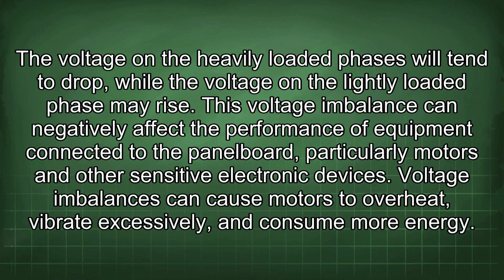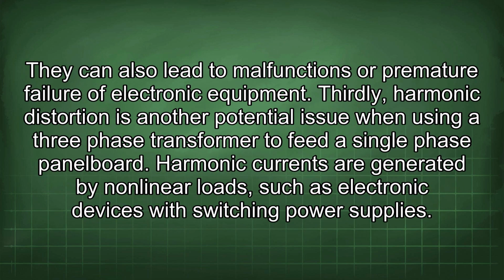Secondly, voltage imbalances can occur when a 3-phase transformer is subjected to an unbalanced load. The voltage in the heavily loaded phases will tend to drop, while the voltage in the lightly loaded phase may rise. This voltage imbalance can negatively affect the performance of equipment connected to the panel board, particularly motors and other sensitive electronic devices. Voltage imbalances can cause motors to overheat, vibrate excessively, and consume more energy. They can also lead to malfunctions or premature failure of electronic equipment.